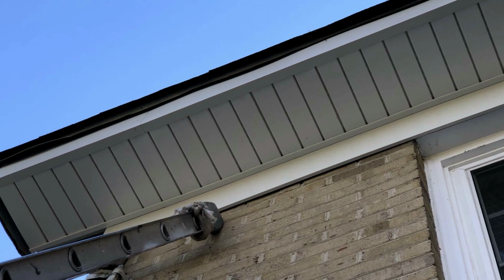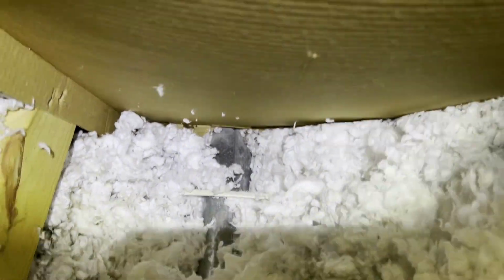Is it Invisivent? I don't know if you know what that is, but I used to love to sell Invisivent when I was doing siding because it's beautiful. It looks clean, but the holes are invisible because they're tucked underneath. As an energy auditor, you need to know to look for that, because if you see those holes, then maybe there's a chance there's going to be good ventilation coming in from the soffit.